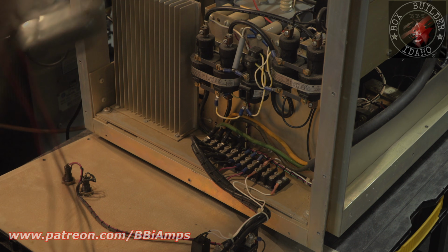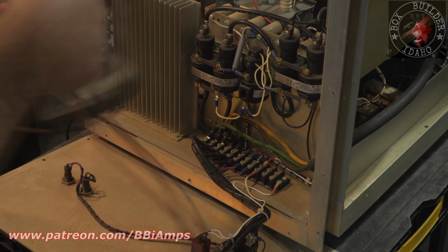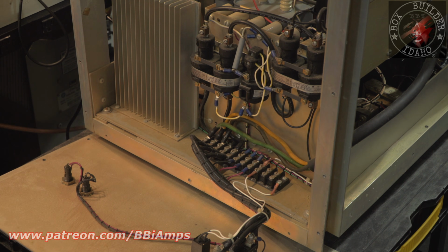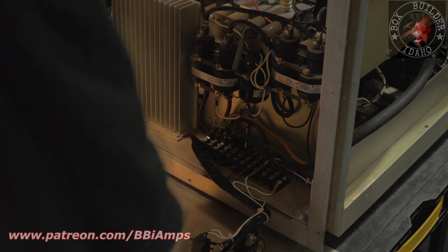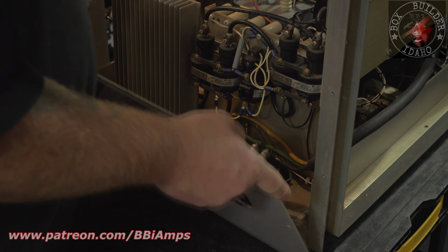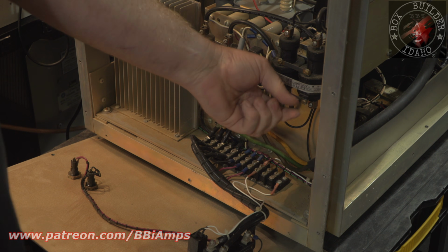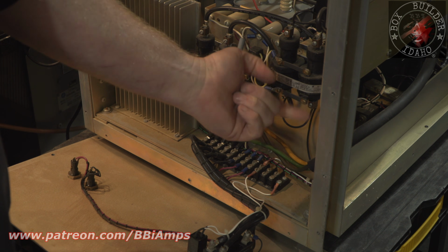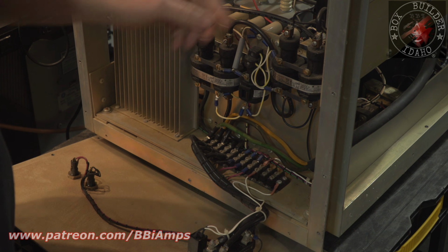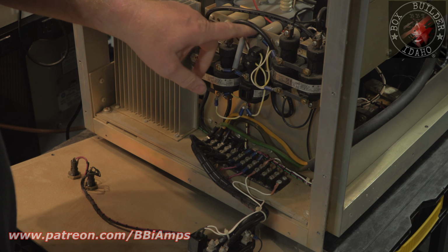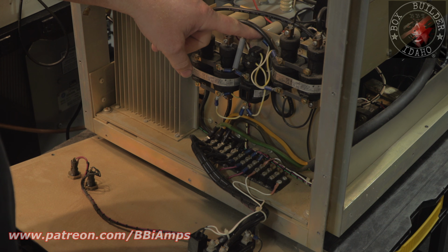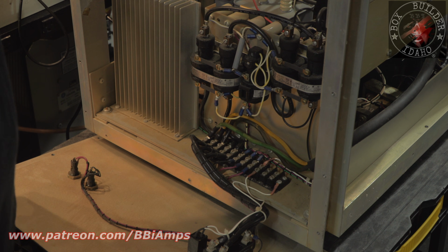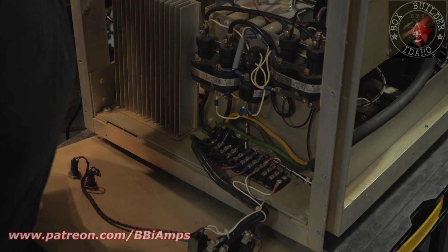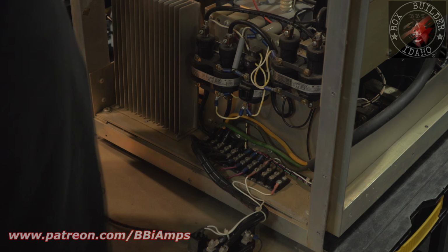So I hope that when they dumped 110 volts on this lead and it shorted out -- this bottom lead that's on this contactor, this one here -- you can see when the cabinet got closed there's only maybe that much clearance between the bottom of the breaker and the contactor, so this wire goes directly to chassis ground. As far as it running back, I don't know -- I don't think so. I really don't think so.